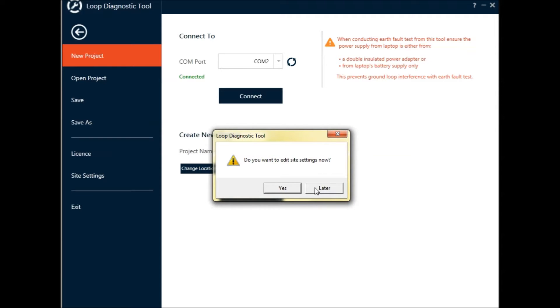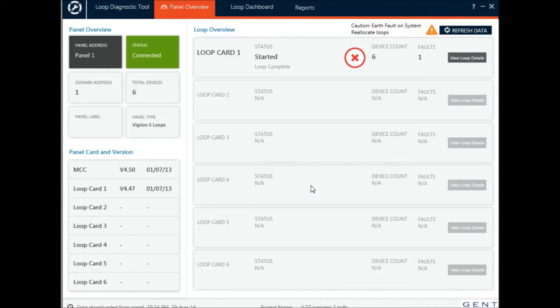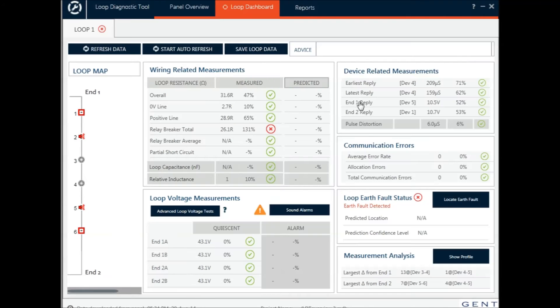I can choose whether or not to edit site settings. I'll choose not to and go straight to the panel. Here we can see that I've connected to a panel that has got an earth fault and has got some faults I've just reallocated, so I will go straight in and look at the loop details.